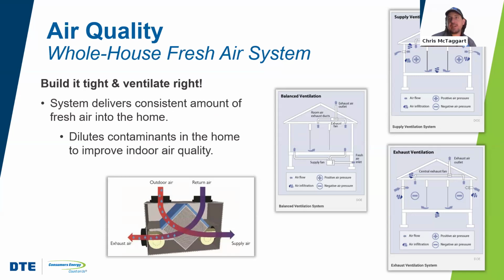Fresh air ventilation system - we're showing here an ERV. You don't have to have an ERV in an Energy Star home, although we'd recommend it and you'd certainly get more credit for it. You're allowed to have exhaust-only ventilation, supply ventilation, or balanced ventilation, and all of those will work. The whole thing is to make sure it's properly sized for the home in question and that it is tested - we have to test the ventilation to make sure it meets the design amount within a reasonable threshold of compliance.